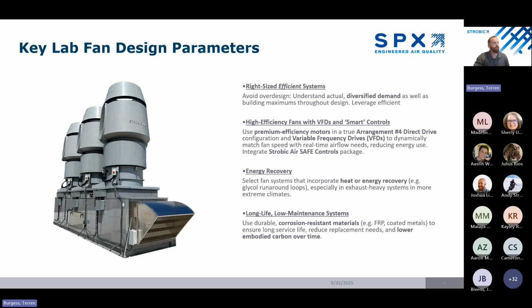So next, we're going to look at the motors, the fan configurations, and the controls. Using premium efficiency motors in an efficient and reliable true direct drive configuration like Strobic Air does, paired with VFDs, is going to allow us to dynamically match fan speed with real-time building needs. Furthermore, with options like the Safe Controller, which is a product that we offer, we can integrate intelligent controls logic to maintain safety while optimizing efficiency. That means we're making the best corrections possible rather than just guessing, right?